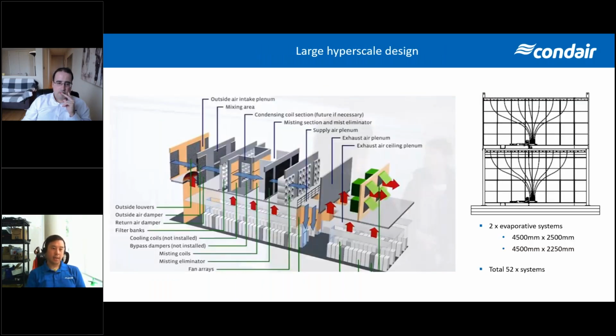And then again, just to show you the scalability of these types of systems, this is a large hyperscale design that we supplied in northern Sweden. You guys may have seen this before, but effectively this was located in northern Sweden, so they were able to take advantage of the colder outside air temperatures most of the year without needing any additional mechanical cooling. But because that outside air was coming in very, very cold, and they were mixing that with the warmer return air from the data hall, the humidity dropped below 5% in some cases. So the adiabatic systems that we put in were primarily to bring the humidity levels back up to about a 20% minimum there.